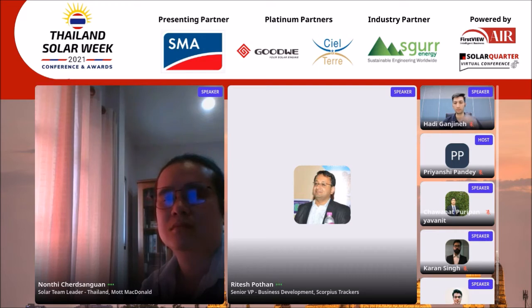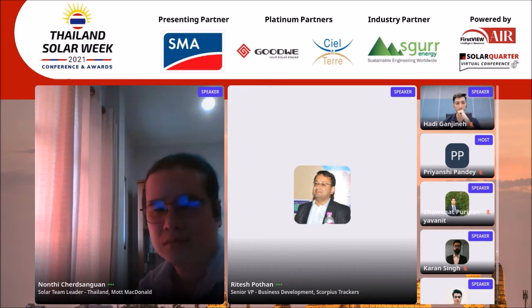That's not how it works. So a 1 megawatt peak for fixed tilt would be 800 or 850 kilowatts for trackers. So actually you save money. And now with panels at 30 cents, you're saving a lot more money. That 10% delta is giving you a 20% gain. Now with bifacial, that's going 25 to 30%. So you're looking at almost a gain of 15 to 20% - you would make more money. So keeping aside that 10% extra you paid, you're making 15 to 20% more. So trackers are a no-brainer.